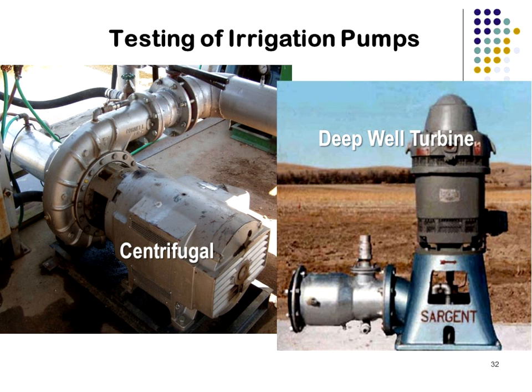The next thing I wanted to cover is testing of pumps. There are two types of pumps that are typically used. One is a centrifugal pump. These are typically used on surface water sources where we have a very shallow water system. The other type is a deep well turbine pump. The centrifugal, this is the pump here. It sits above the water, and it basically has to draw the water up in the inlet tube. These can be two types, non-priming and priming type.